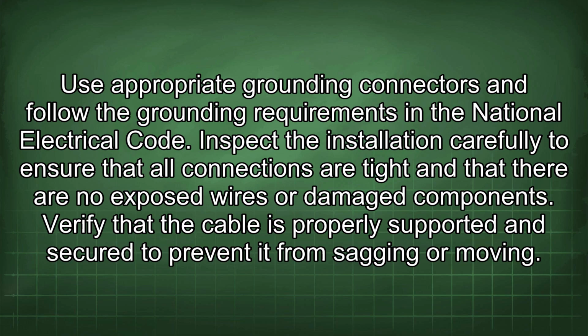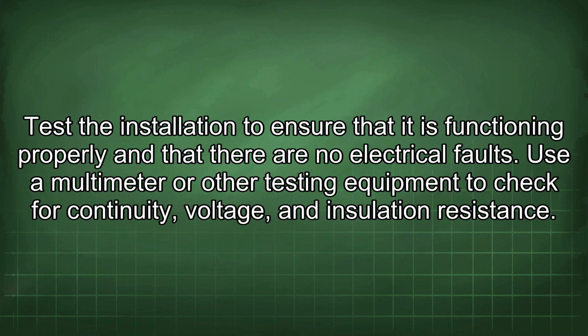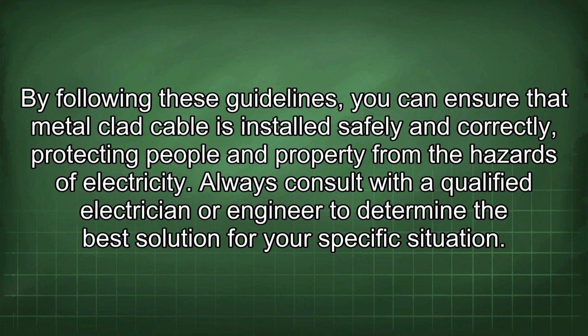Inspect the installation carefully to ensure that all connections are tight and that there are no exposed wires or damaged components. Verify that the cable is properly supported and secured to prevent it from sagging or moving. Test the installation to ensure that it is functioning properly and that there are no electrical faults. Use a multimeter or other testing equipment to check for continuity, voltage, and insulation resistance. By following these guidelines, you can ensure that metal-clad cable is installed safely and correctly, protecting people and property from the hazards of electricity.